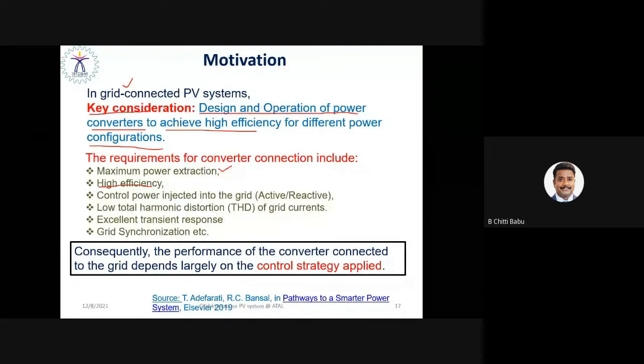Moreover, the power that will be injected into the utility grid must be controllable. Controllable means in terms of active and reactive power. All of us know that the active power and reactive power must be controlled independently, and instantaneously, in order to regulate both grid voltage and grid frequency. Because grid voltage is very essential to maintain the voltage profile constant.